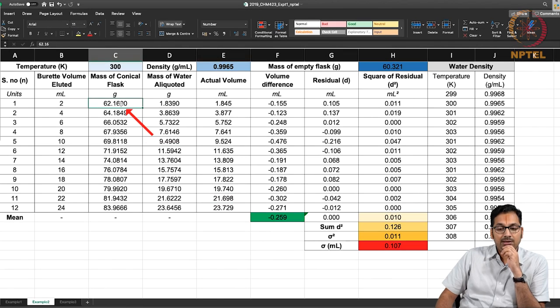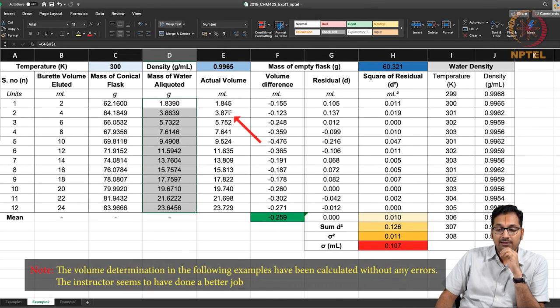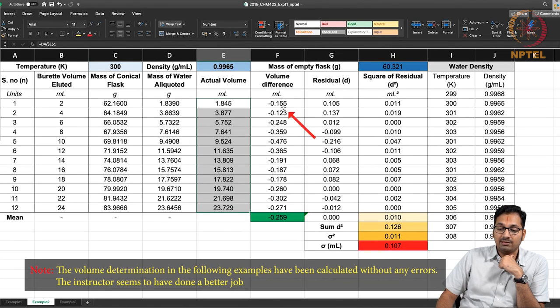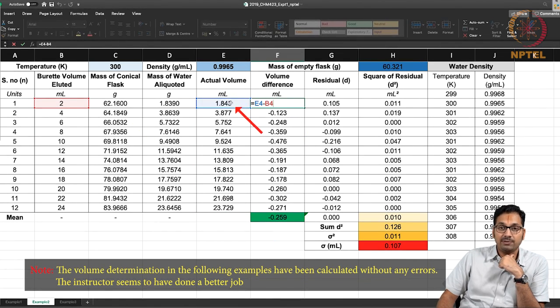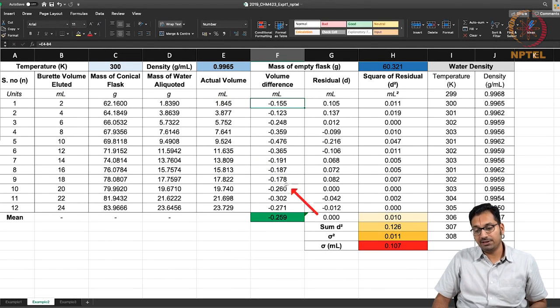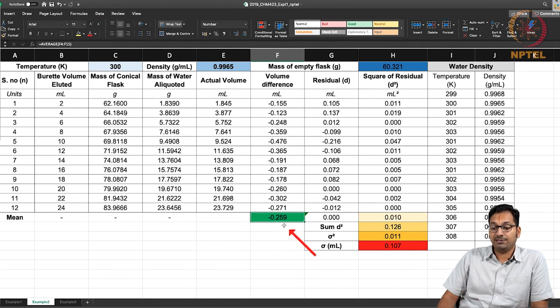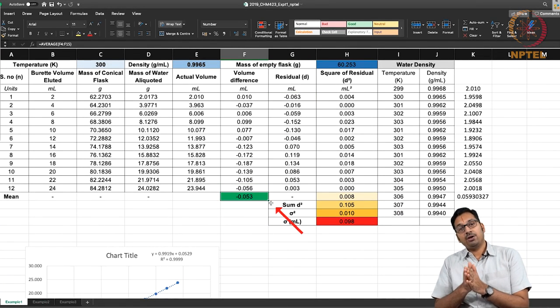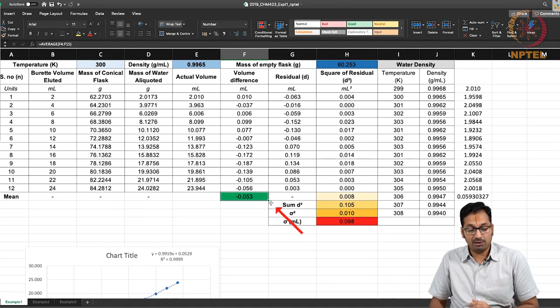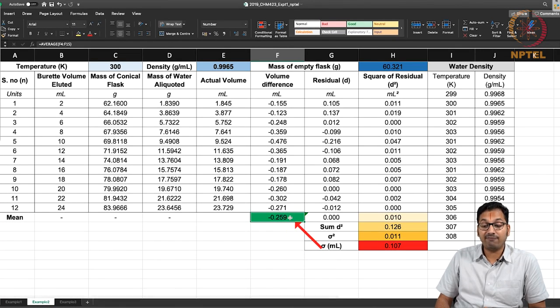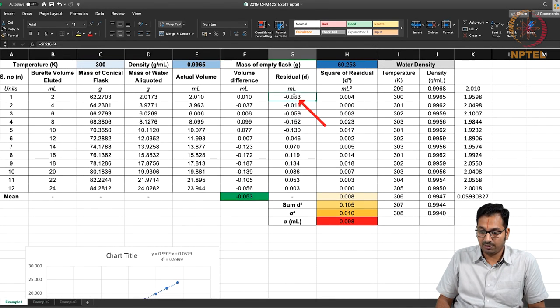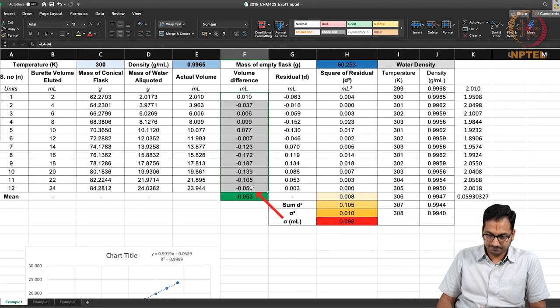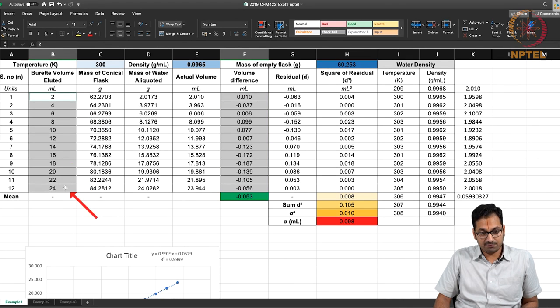Let us take another example where I have already done all the necessary math using similar formulae. Here the experimentalist measured all these values again, determined the mass per aliquot, converted it to volume based on density, found the difference between what aliquot was added and what was expected — done for each step. You are able to realize the average volume difference comes up to minus 0.26. In the previous case you had something very close to 0, indicating a reliable and precise way of adding aliquots, but here you can see the average is quite far away, indicating the measurement is erroneous.